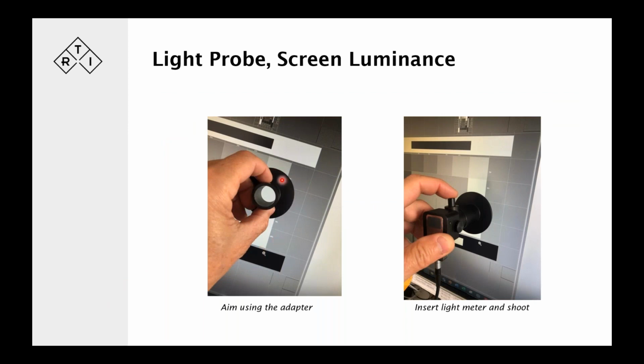There is a bit of a shield or a shading device to reduce the risk of getting any side light interfering with the measurement. And that doubles as an aim, so you can aim it this way and then pop the tube for, say, a monitor light into there and press to open that shutter and expose the detector for that light. And then you release the shutter, move to the next area in the test image, and keep going, and you're done.